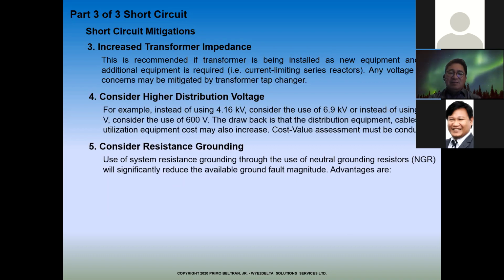At the same time, you don't inject those currents to the grid. Dumadaan sila sa effective ground return path conductors natin, pabalik sa neutral. Hindi po katulad ng mga medium voltage equipment, nasa labas sila, so meron kayong ground grid.